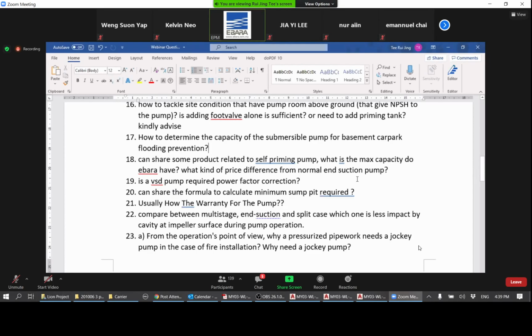Number 18. What kind of price difference from normal end suction pump? Well, definitely a bit more expensive, simply because an end suction pump is quite a straightforward pump. But a self-priming pump has another chamber, let's say, to expel the air and all that. So the volume of such a pump is also less. So that means basically the cost is more. So it depends on, again, the model and the flow rate and the head.